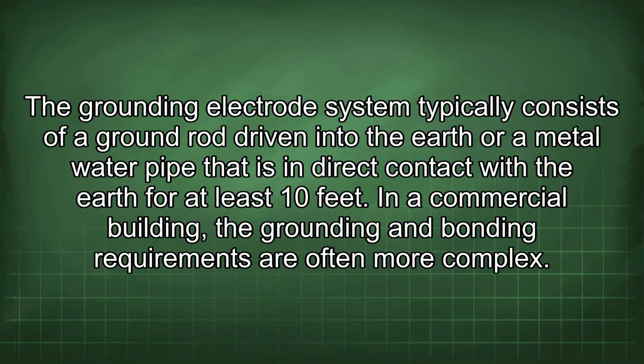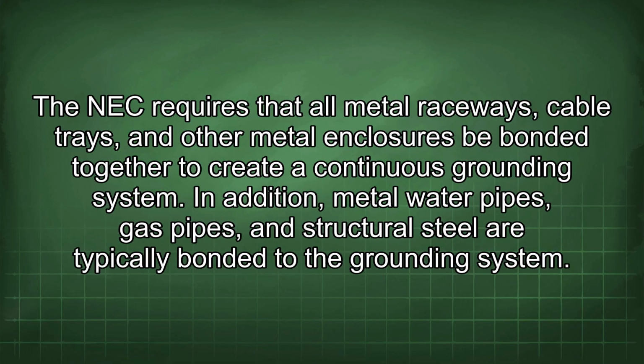The grounding electrode system typically consists of a ground rod driven into the earth or a metal water pipe that is in direct contact with the earth for at least 10 feet. In a commercial building, the grounding and bonding requirements are often more complex. The NEC requires that all metal raceways, cable trays, and other metal enclosures be bonded together to create a continuous grounding system. In addition, metal water pipes, gas pipes, and structural steel are typically bonded to the grounding system.